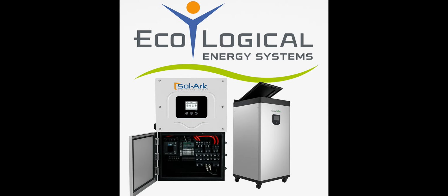Wow, okay. And finally, the size of your system matters. The warranty explicitly warns that using an inverter that charges the battery at a rate that's too high can actually cause it to break down. And that won't be covered. Correct. Yeah. They even refer you to their minimum recommended battery sizing standard document. This really highlights how important it is to make sure your battery capacity is properly matched to the power output of your inverter. Okay, let's switch gears and talk about the SolArk inverters.